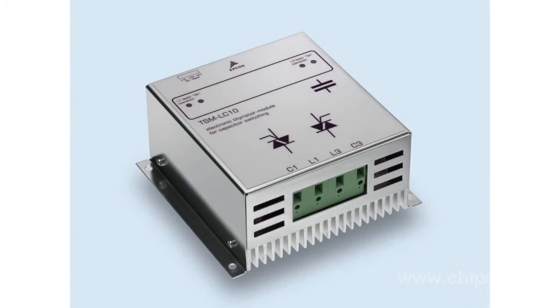These types of thyristor modules can be best controlled by a high-speed regulator like the BR-6000T. However, the condenser stages should be used with special powerful discharge resistors. Discharging chokes and steady ceramic discharge resistors are strictly prohibited.